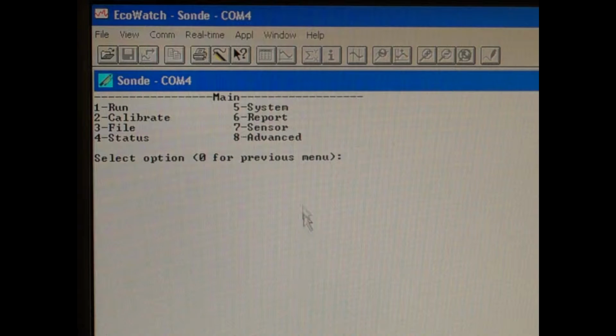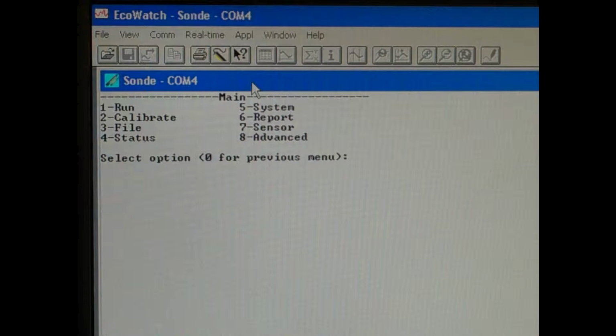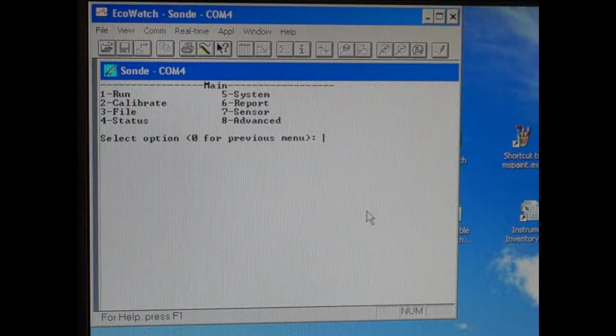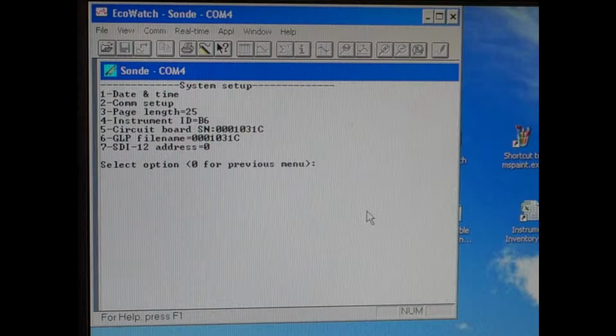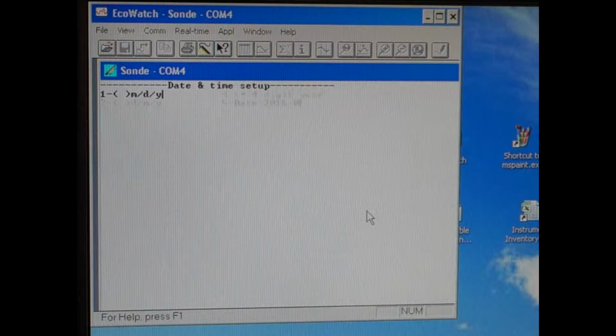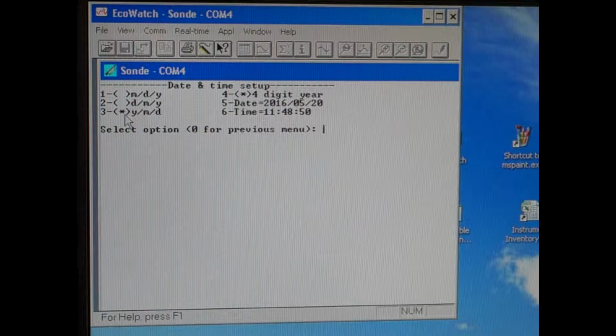Now this should come up with the Sonde menu. This is actually from the Sonde itself. The first thing we're going to do is check the date and time, and check the battery status to write that down on our calibration sheet. So we're going to hit 5 for system, and then we're going to go to date and time. The first thing I want to find out is that it's in year, month, day form, and that's selected already with 3. Right now the date is correct. It says 2016 May 20th, but in order to change it you would just hit 5 and you could change that.